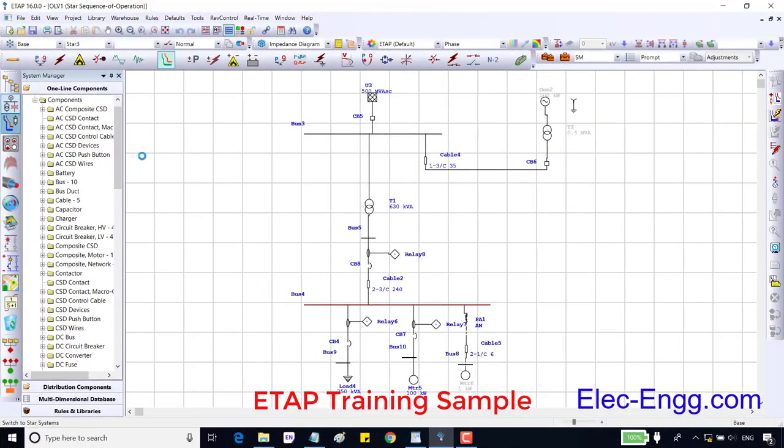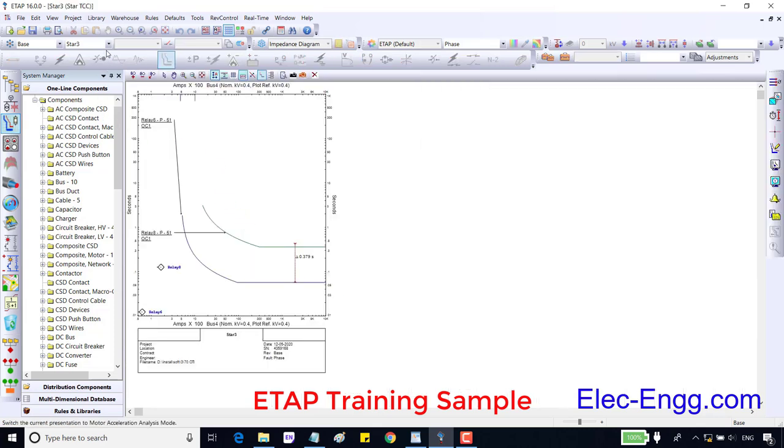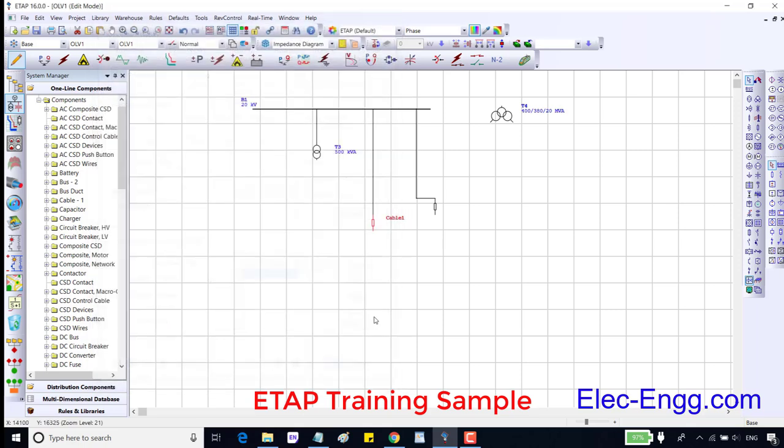In the previous session we set the time delay overcurrent phase or ANSI 51. In this session we are going to set the instantaneous phase overcurrent or ANSI 50. If we select FLA of an element, or full load ampere of an element, then we can select the current of which element should be considered for cable sizing. Let me show you this with an example.